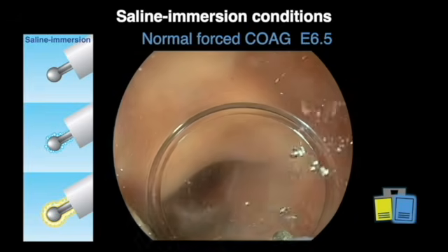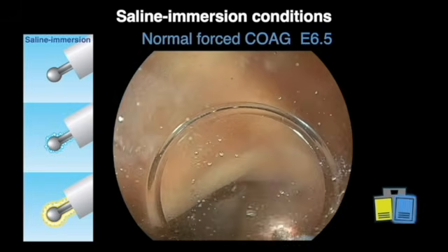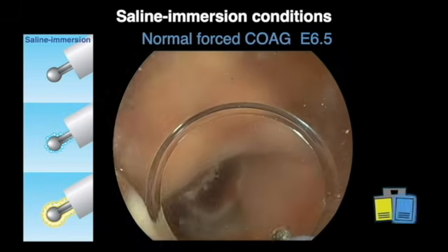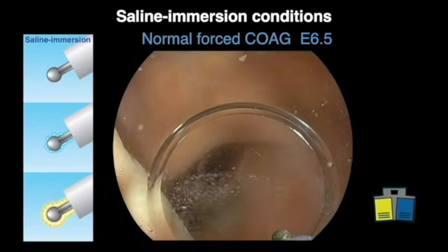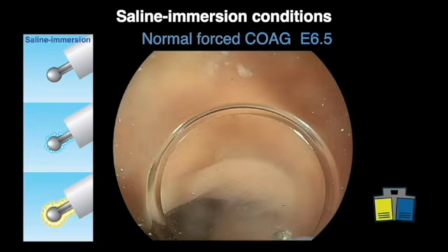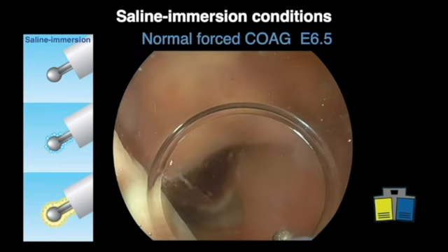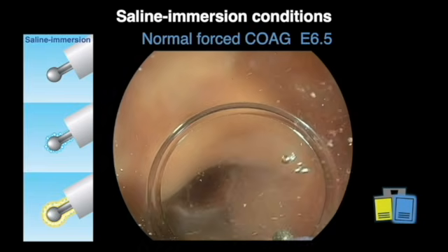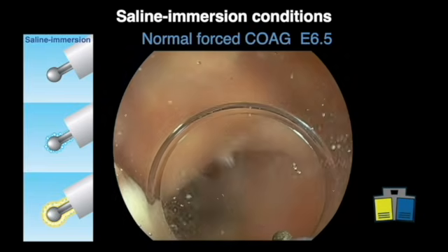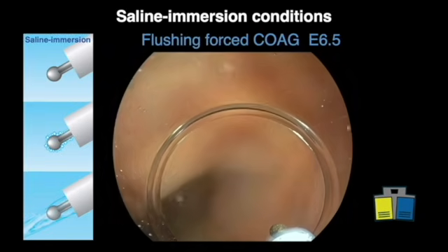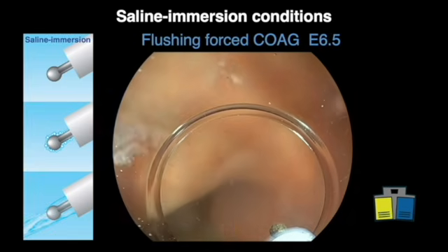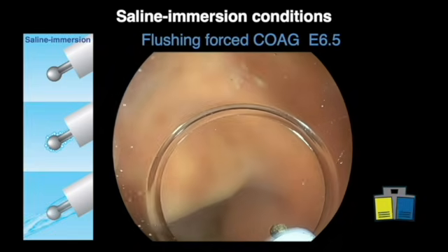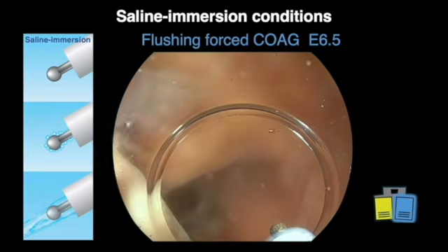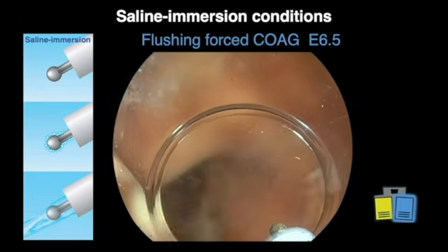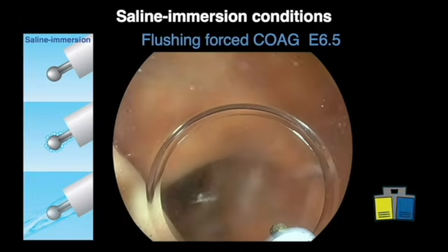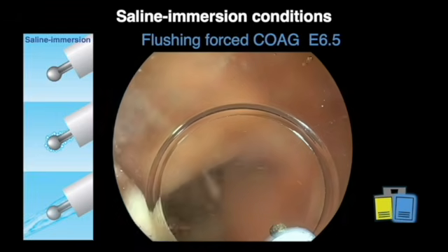Under saline immersion conditions, normal forced coagulation creates a vaporization layer of bubbles around the device. This forms an electrical gap and leads to discharge as evidenced by a spark around the needle-type knife. When the video is played in slow motion, the bubbling and spark are more apparent around the tip of the knife. In contrast, with the flushing method, this vaporization layer is instantly cleared by saline flow from the jet of the knife. This suppresses electrical discharge even at high output coagulation settings and enables a more pure coagulation without a spark.